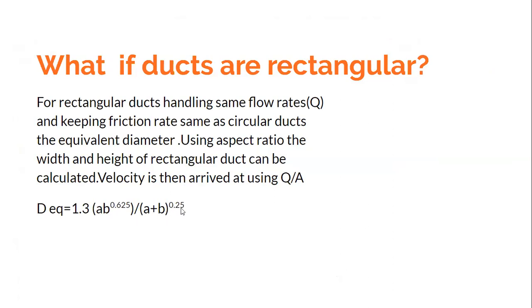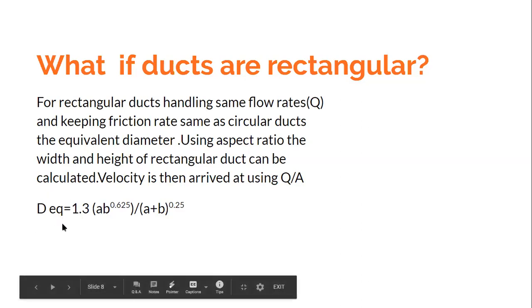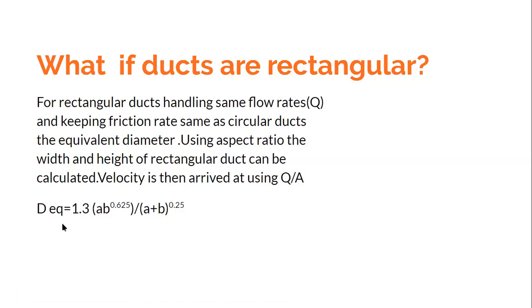The empirical relation is: equivalent diameter = 1.3 × (a × b)^0.625 / (a + b)^0.25, where a and b are the width and height of the rectangular duct. I won't go into the theory behind this expression. For practicing engineers, it is enough to use this expression. Having obtained the equivalent diameter from the friction chart, by fixing either the height or the width, or by fixing the aspect ratio (width-to-height ratio), you can calculate both dimensions a and b of the rectangular duct.